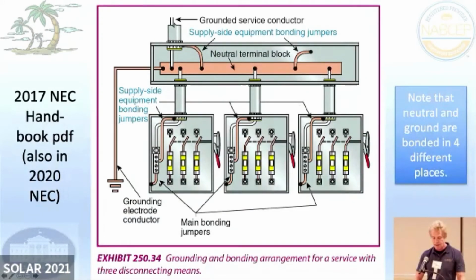This is from the NEC handbook. We're just showing how you have multiple services on a building, like three different apartments. What they do here is bond neutral to ground, so there's a white wire and a bare or green wire in three different places. That's pretty much the best way to do it anyway for a supply side connection, because you're all on the supply side of overcurrent. There's no overcurrent protection device between you and whatever is coming from the utility. There could be something at the transformer, but it's not something that we consider. And so you do it differently.